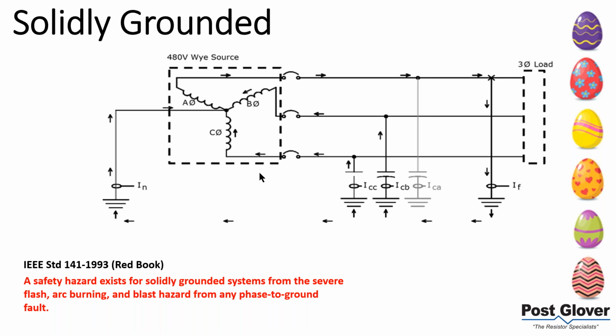because of the high fault currents. Because of the low impedance, you have these high fault currents that can occur. Arc flash, arc blast. As you can see, the Red Book talks about how you get severe arc flash burning from any phase to ground fault. So we really need to think through where we use solid grounded. It does well at finding the fault, clearing the fault potentially, because there's a high level of indication potential there. However, it can cause damage. The arc flash probability is higher because of the amount of energy, etc.